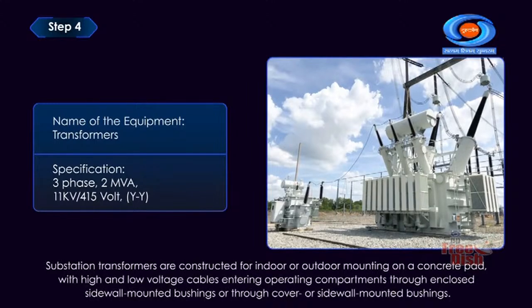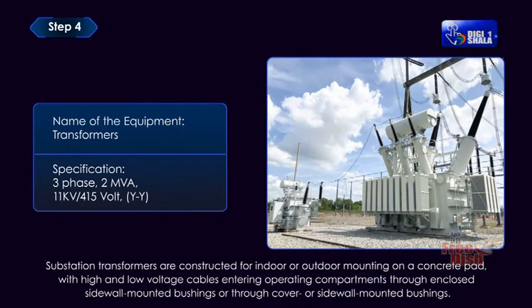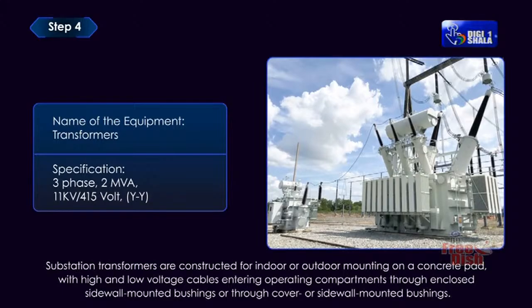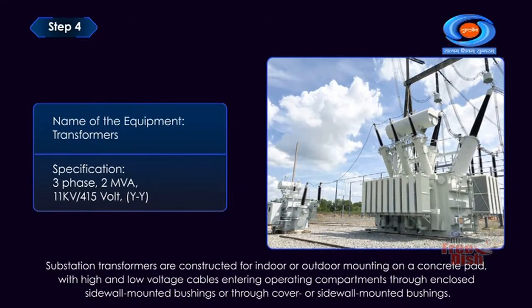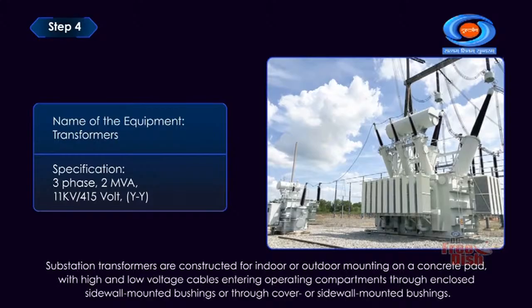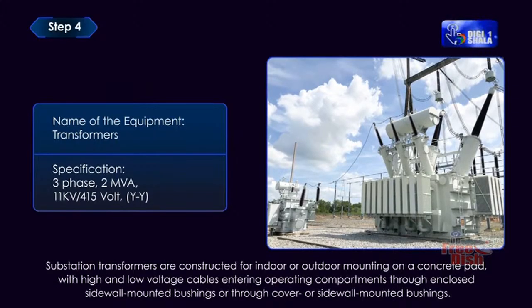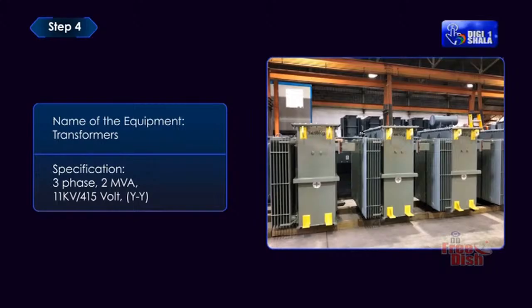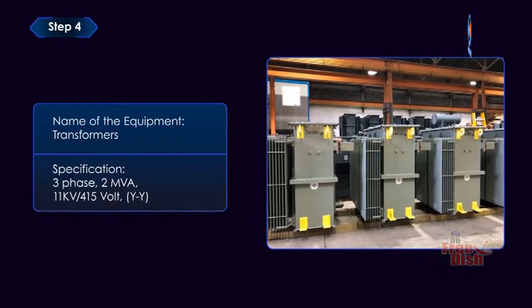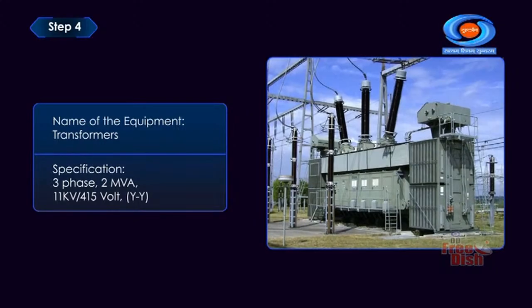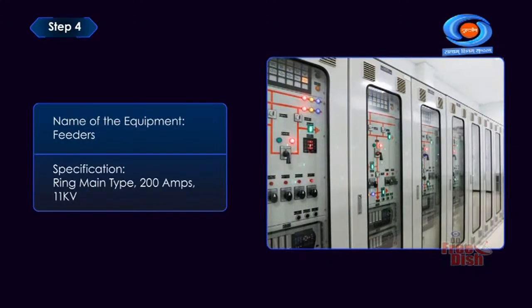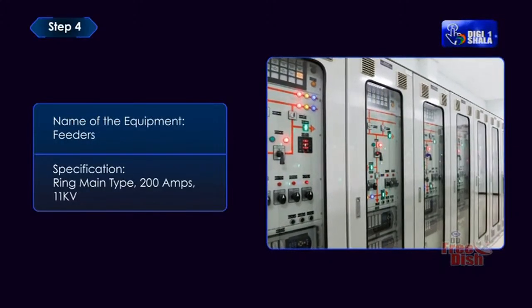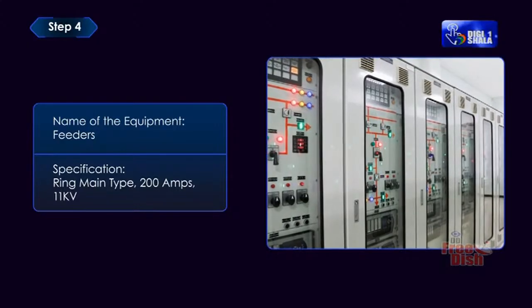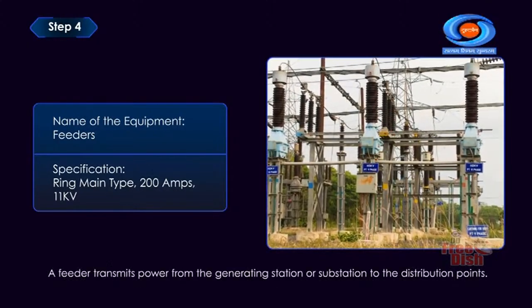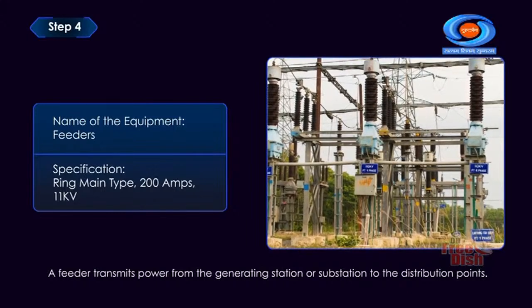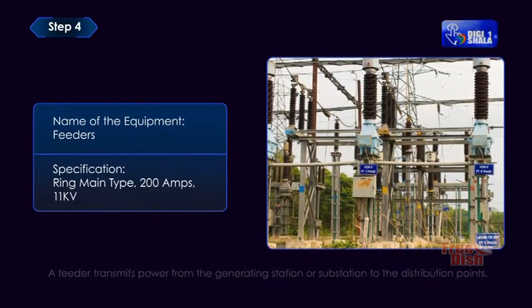Substation transformers are constructed for indoor or outdoor mounting on a concrete pad, with high and low voltage cables entering operating compartments through enclosed sidewall mounted bushings, unit type transformers, or through cover or sidewall mounted bushings, open type transformers. Feeders: ring main type, 200 amperes, 11 kilovolt. A feeder transmits power from the generating station or substation to the distribution points.